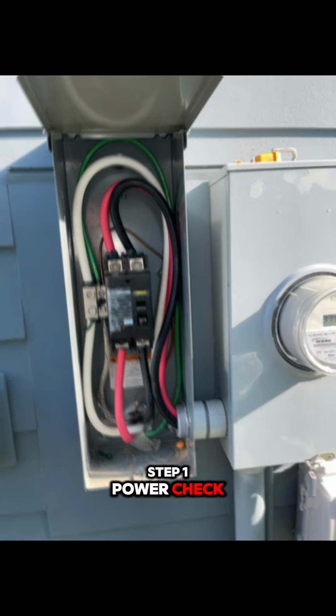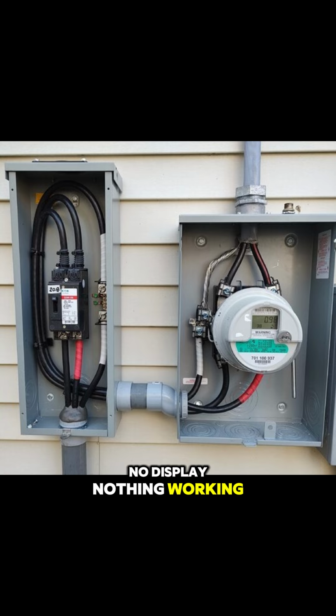Step 1. Power check. No display? Nothing working? Start at the breaker panel and the disconnect outside. Make sure you have high voltage feeding the unit.